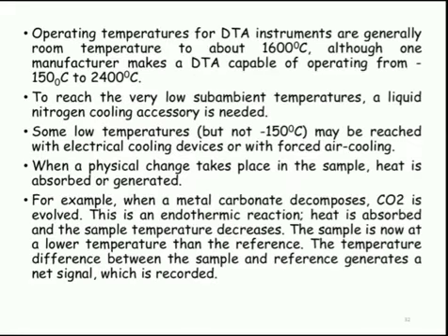So the operating temperature for DTA instruments is generally room temperature to about 1600 degrees Celsius, although one manufacturer makes a DTA capable of operating from minus 150 degrees Celsius to 2400 degrees Celsius. To reach the very low subambient temperatures, a liquid nitrogen cooling accessory is needed. Some low temperatures, but not minus 150 degrees Celsius, may be reached with electrical cooling devices or with forced air cooling.